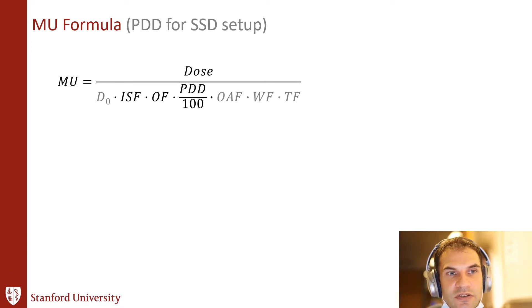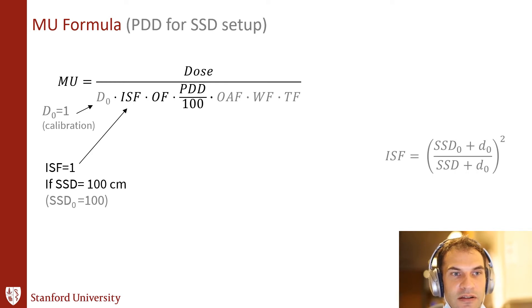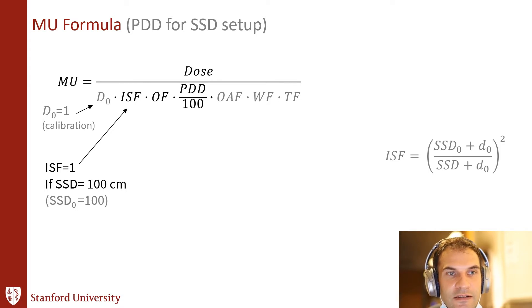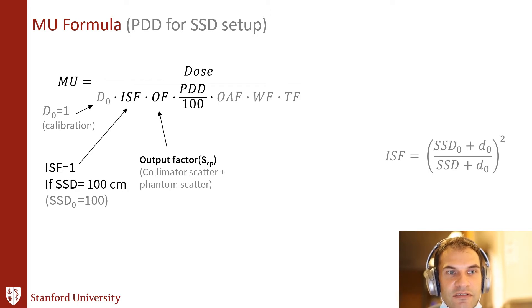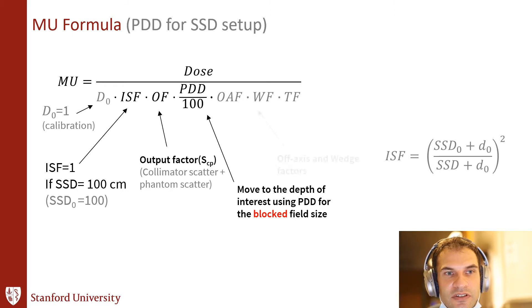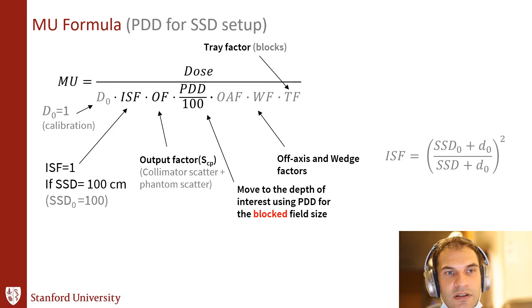The MU formula for photons for PDD or SSD setup is as follows. The MU equals the prescription dose — the dose rate is 1 if you have good physicists. There's an inverse square factor which accounts for conditions where you're treating at a different SSD other than the calibration SSD. If you want to move away from a 10 by 10 field size, you use an output factor other than 1. If you want to move down in depth, you adjust the PDD. You can also adjust for dose off-axis, wedge, block, or tray factor.